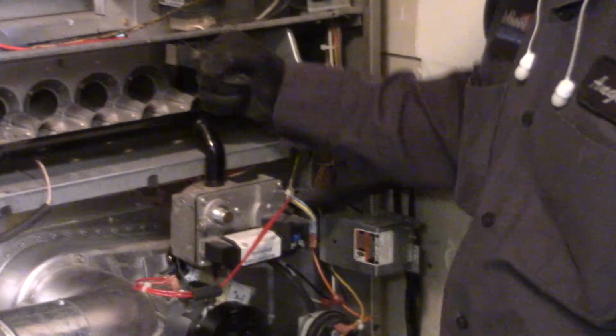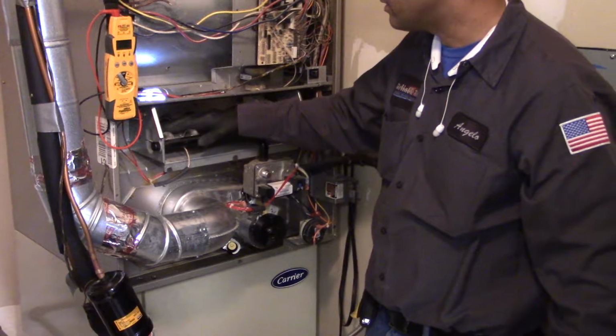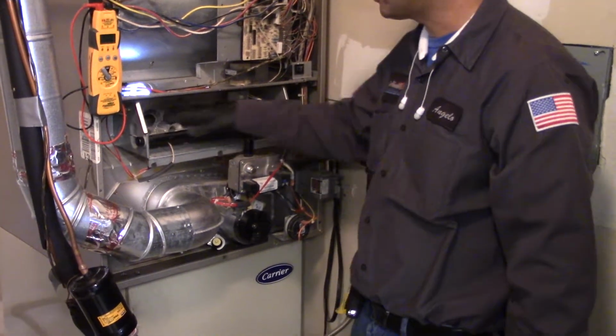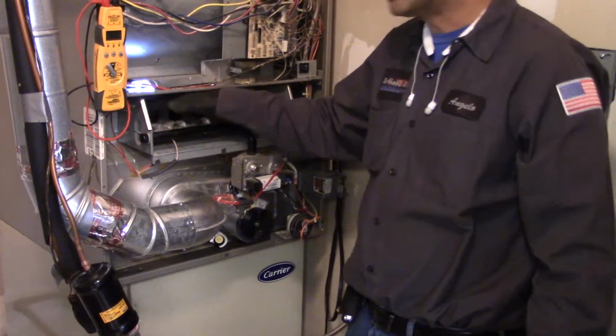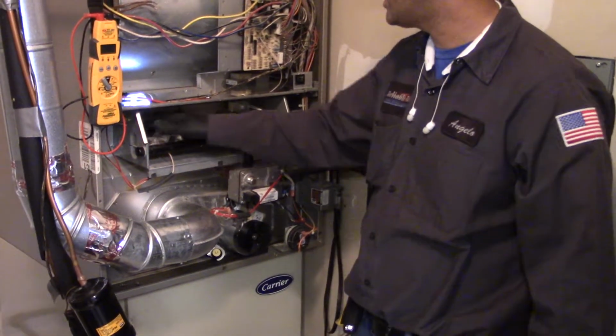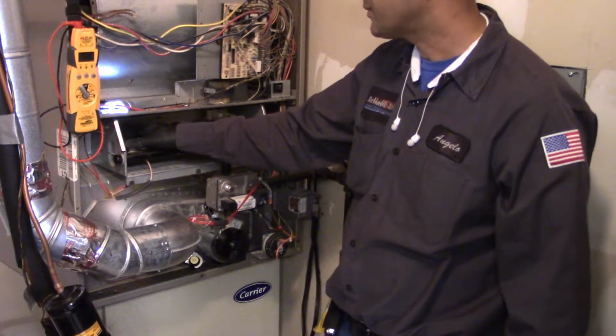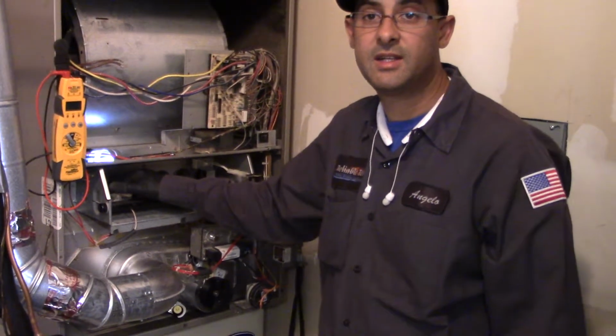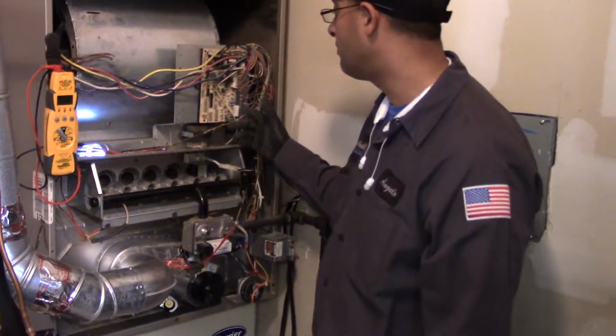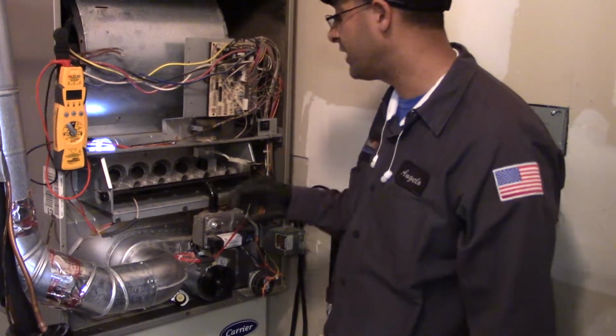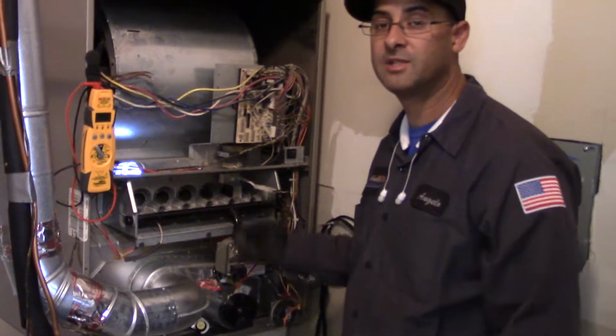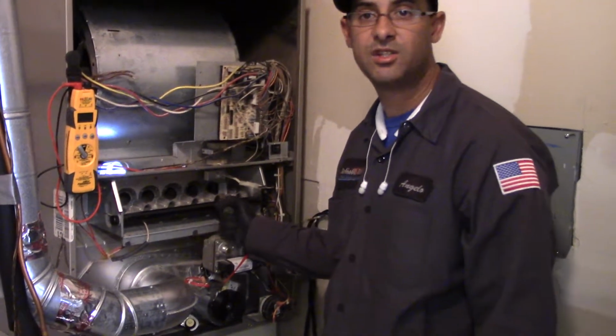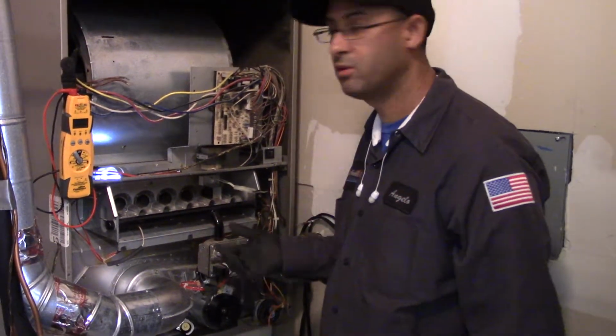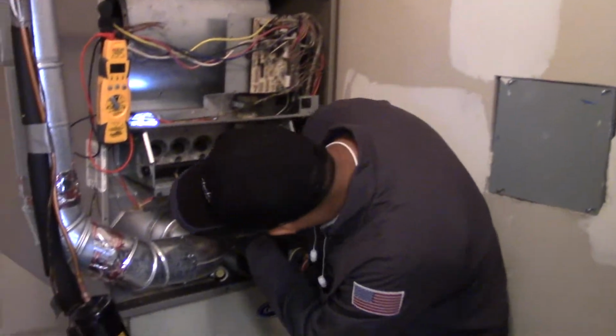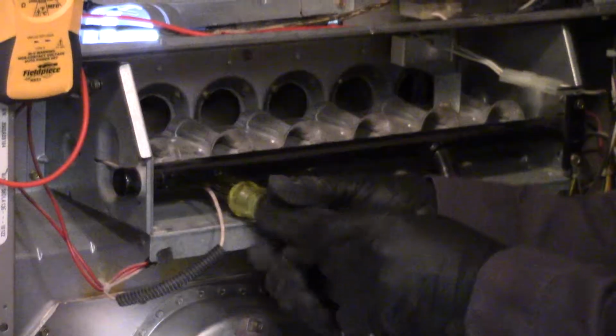And the reason why that's important is when the system fires up for the first time and the flames are lit, if the last burner is clogged or there's something going on in here, or maybe the gas valve opens up and it doesn't light, the flame is not going to be detected. But even if it does light and we got a blockage here and the flame doesn't, let's say, get to the last burner, then it's not going to be detected. So what happens is this flame sensor will tell the control board that there is no flame, so please shut down the gas valve and don't allow the system to run. It'll try a couple of times, I believe it's 3 times, but it's more of a safety mechanism to make sure that the gas valve doesn't continue to run, so there's obviously not an explosion and nobody gets hurt. So on this flame sensor, what we run into quite a bit is that they get dirty after running all year long.